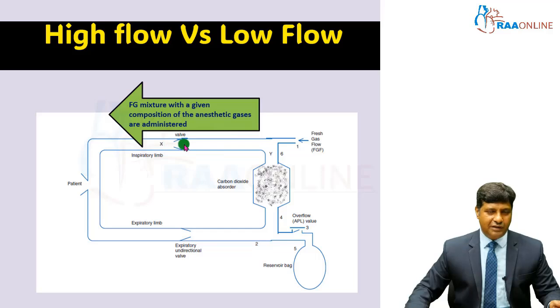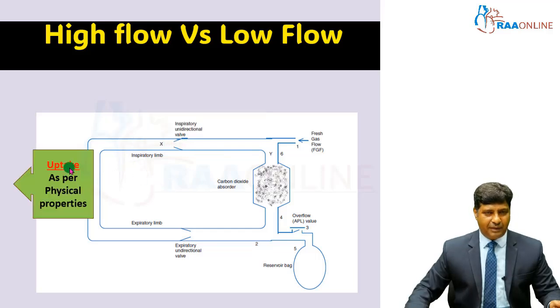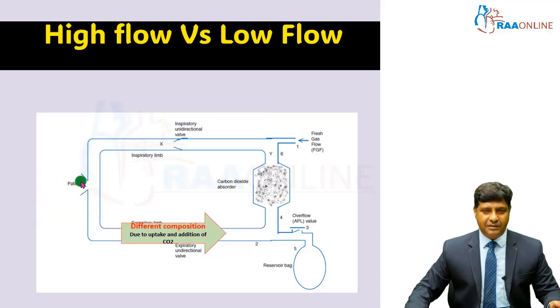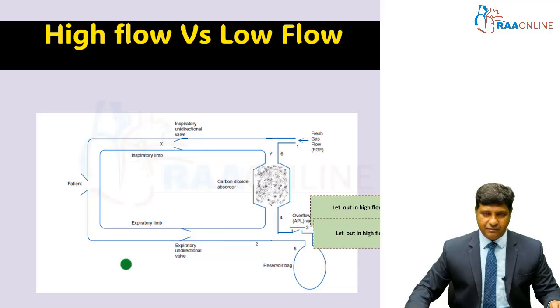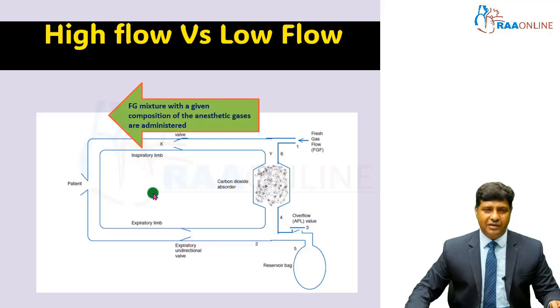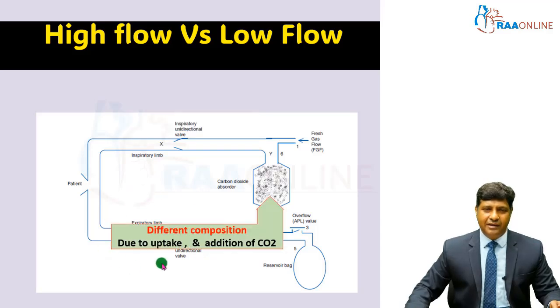The gases enter the inspiratory limb through the unidirectional valve, then some of them are taken up as per their physical properties, and the remaining gas comes back from the lungs into the expiratory limb. If the flow is much higher than or equivalent to the minute volume, the majority of gases are vented out. But when we reduce the flow, after the uptake, the exhaled gases are rerouted back into the circle absorber.